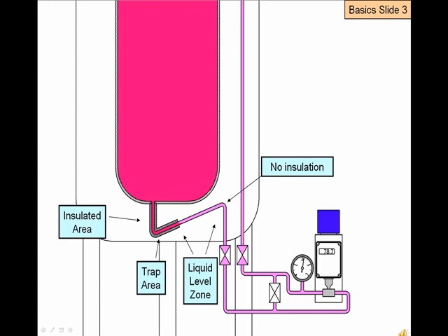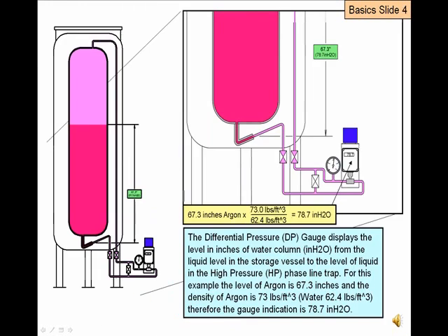The HP line design is key in making the differential pressure gauge read accurately. Over the years, the design of this line has changed due to insulation systems and the need for more accurate measurement. The graphic shows an HP line that has a 10-inch trap section with the bottom of the trap insulated and the majority of the trap section exposed. This bare pipe section helps maintain the liquid height within this zone. This example has a measurement of 67.3 inches of argon above the liquid in the trap.